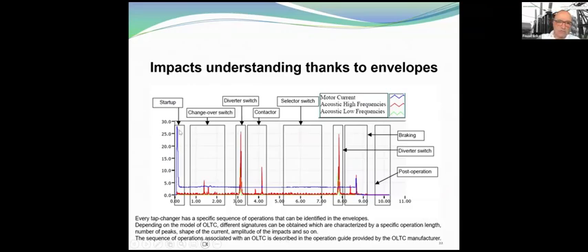Here you can see in blue the startup of the motor current. In blue you have the motor current, and here in red you have the high frequency envelope, and this is the part of the changeover switch, diverter switch, the first sequence. Here some contactor is acting, the selector switch is silent. Here you have a diverter switch, because, as you see typically here, it's two transitions. And then after you have the braking part, which is also important to analyze. And then after you have the post operation.